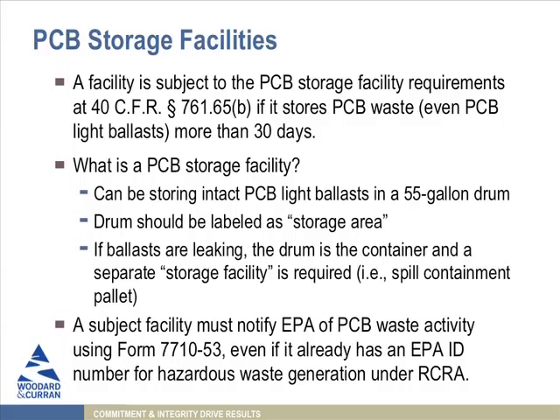So if your campus is generally dealing with light ballasts, and you put them in a drum, and you're not dealing with transformers, the gentleman I spoke to from Region 4 may be correct that in Region 4, all you need is a closed drum. But to be safe and conservative, this is what the regulations do require: if you're going to hold it for more than 30 days, make sure it's got a berm, make sure it's got walls and a roof, and make sure it's on a flat, impermeable, non-porous surface.